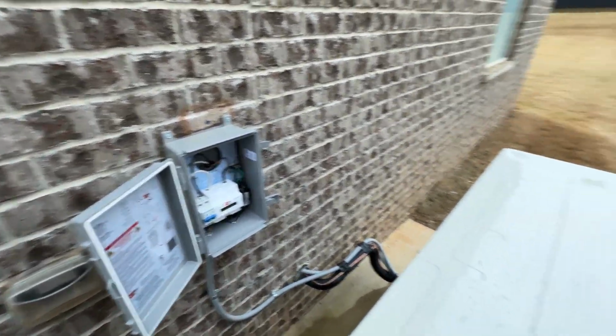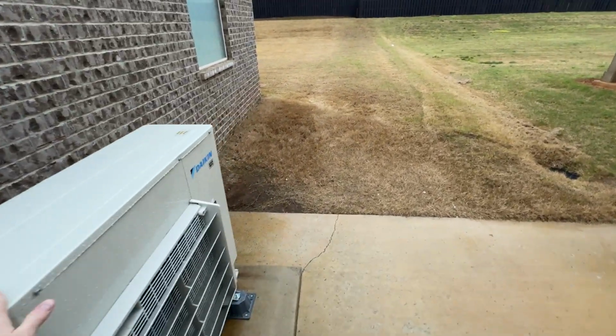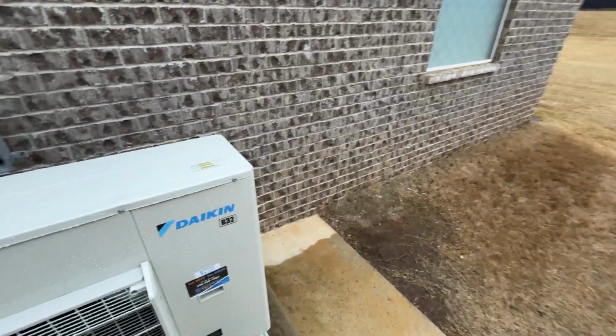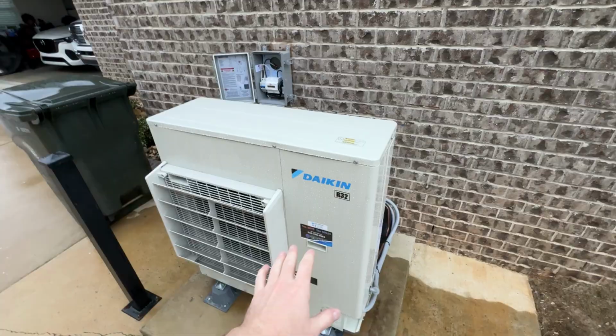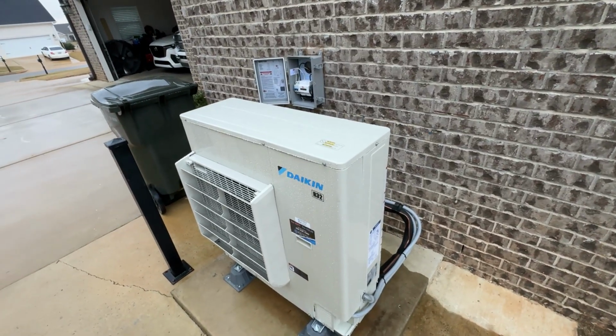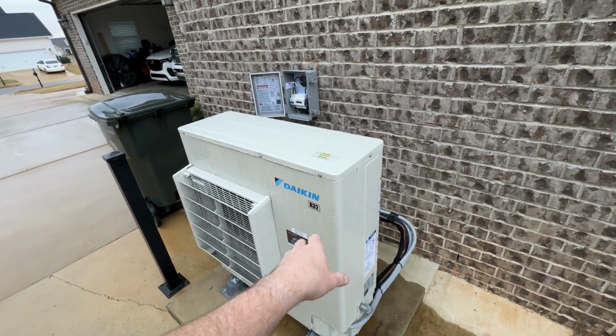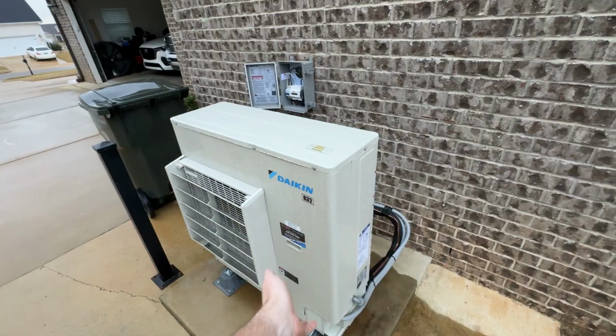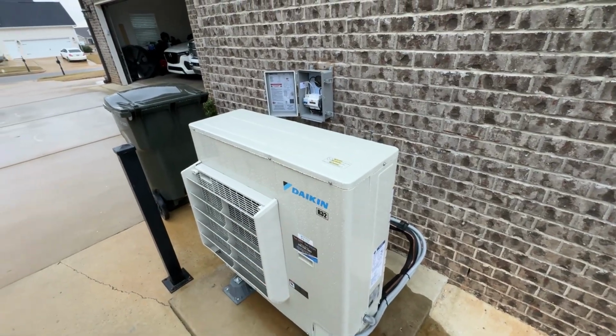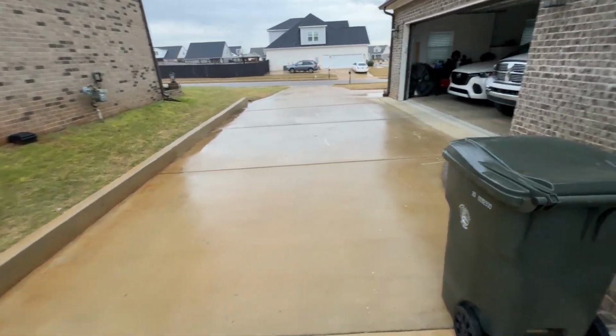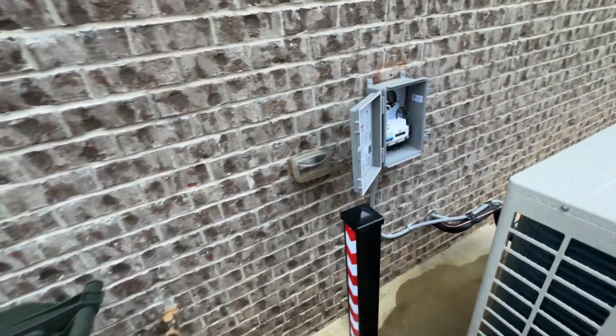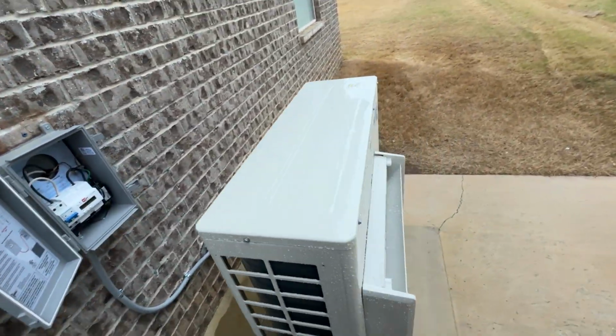I was over that. And these Daikins, because they're inverter drive and they have delicate circuitry in here, have trip protection at 253, where they will turn themselves off and not run because the voltage is too high and it'll end up frying that board. That board's a $6,000 board, so you don't want that. Let me get out of that Airstream. It's running like crazy. I got heat again.